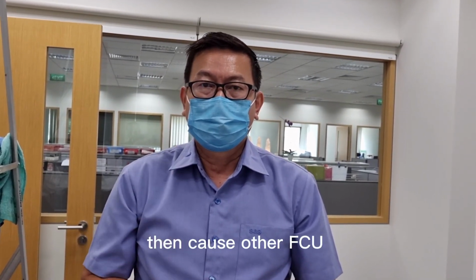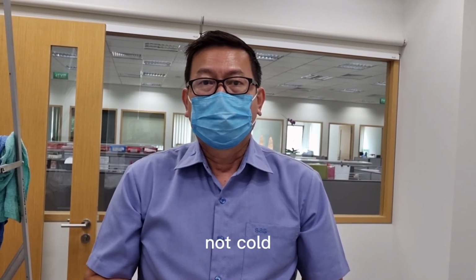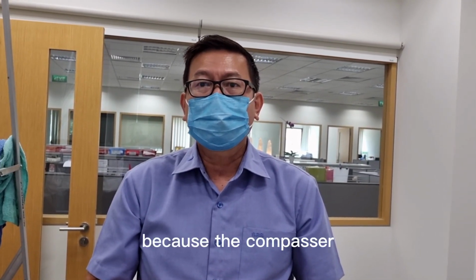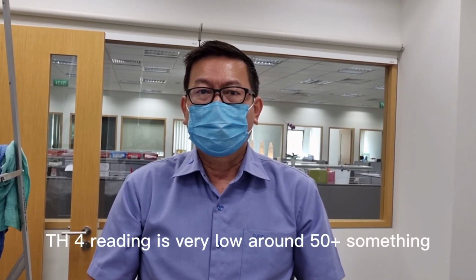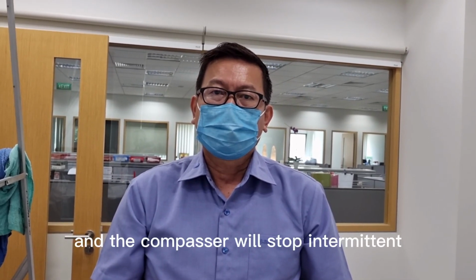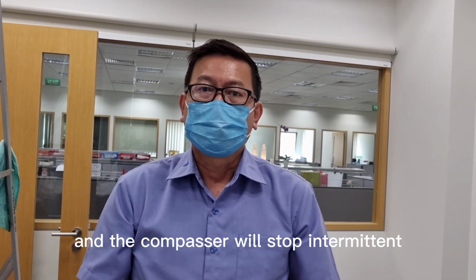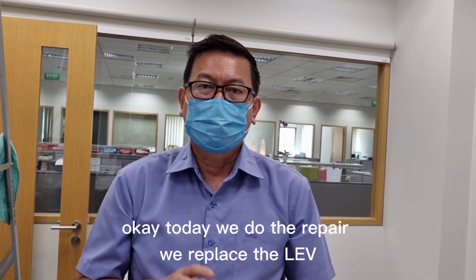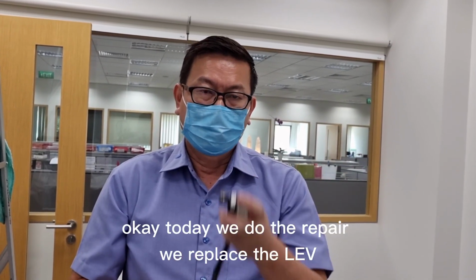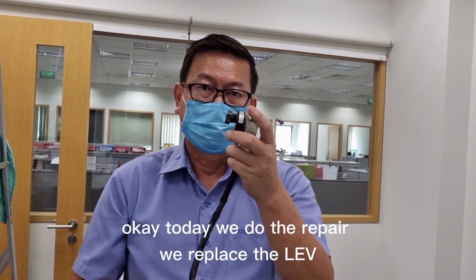Because of this, the unit is not cooling. The compressor TH4 reading is very low, around 50 something, and the compressor stops intermittently. Okay, today we do a repair, we replace the LEV valve.